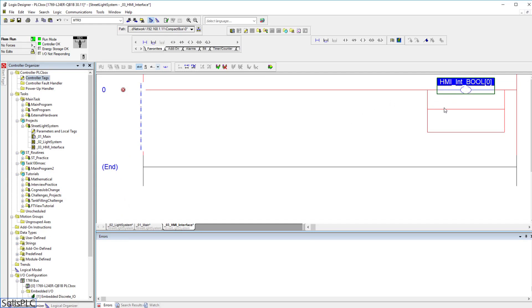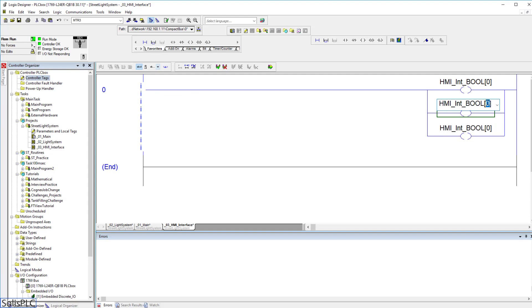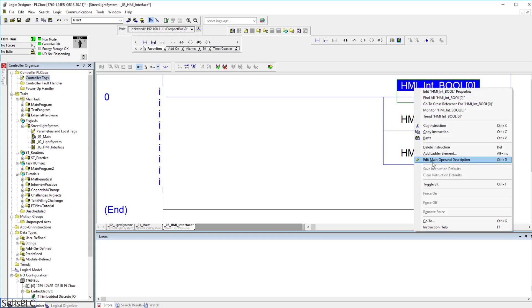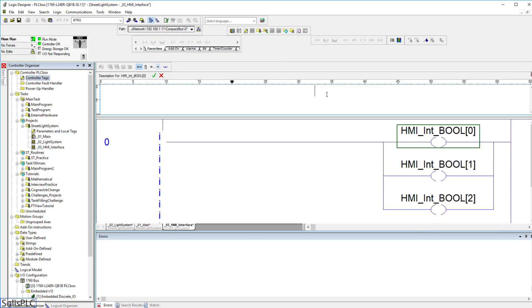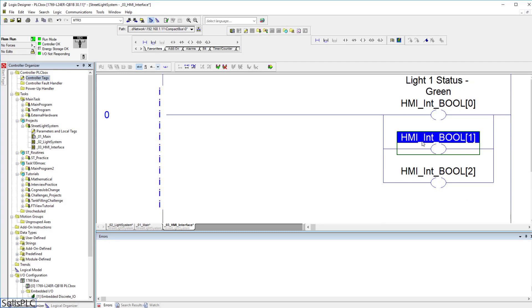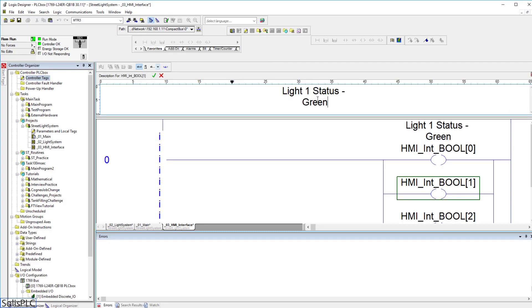Going back into the routine, I'm going to utilize three distinct booleans to specify the status of those lights for the HMI. A very good practice is to not leave these booleans unnamed — you can right-click and go into edit main operand description or use the Ctrl+D shortcut. This gives you the option to give the specific tag a description. So here we're going to type in 'light1 status green', so when this is energized we know light1 is in a green status. I'll use Ctrl+D and Ctrl+V to add descriptions for the next two: 'light1 status yellow' and 'light1 status red'.